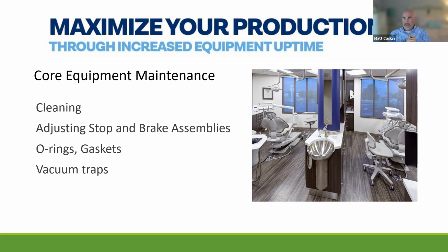But they do tend to loosen up over time, and they do require adjustment. There's gaskets, O-rings, water valves. If you look on the floor, you can see the foot control. There's toggle valves on there. They're made out of plastic, and you kick them 200-300 times, and they tend to break off. And so they do require regular maintenance.